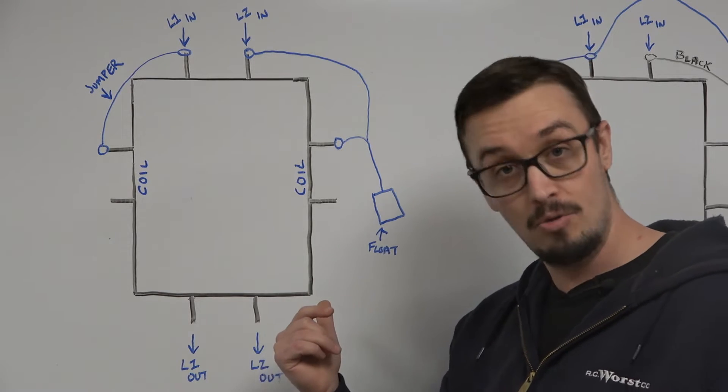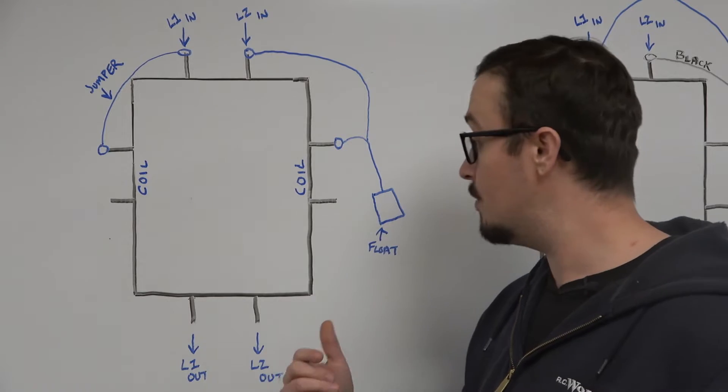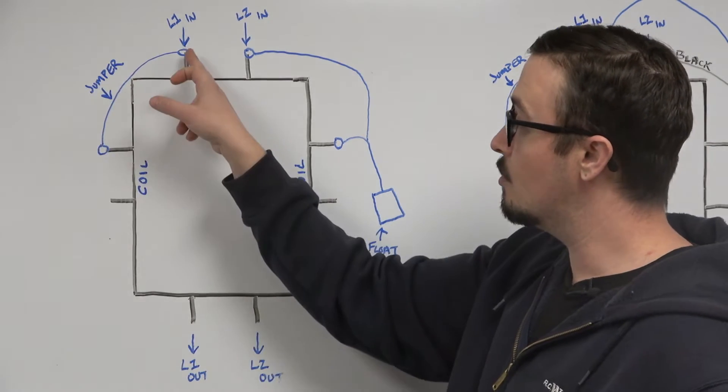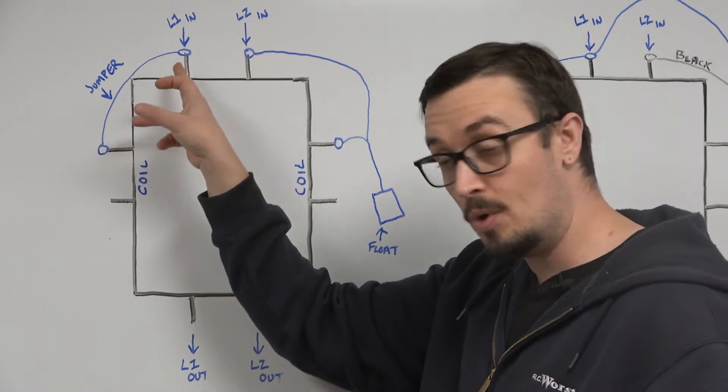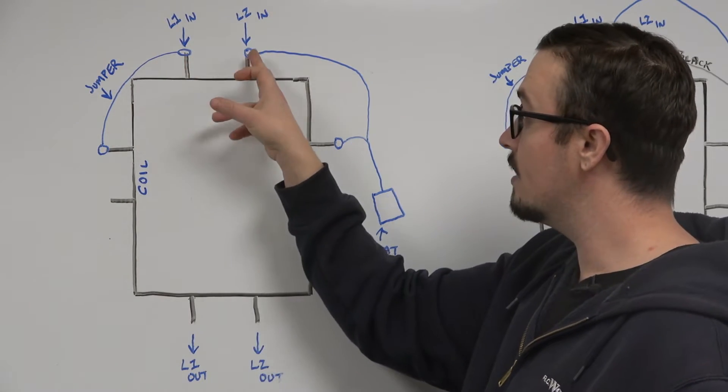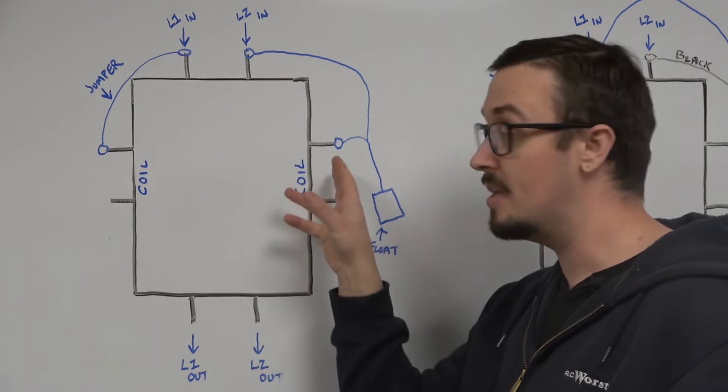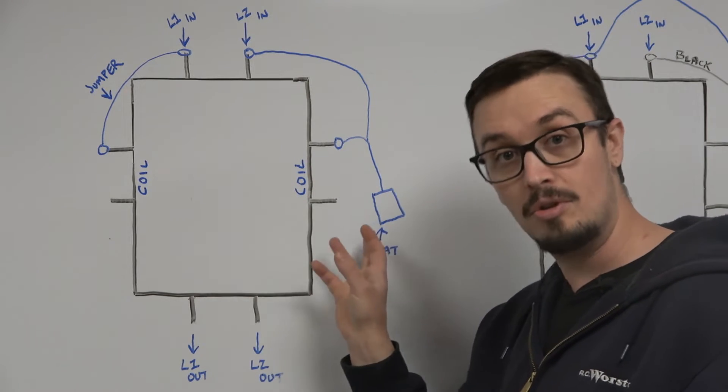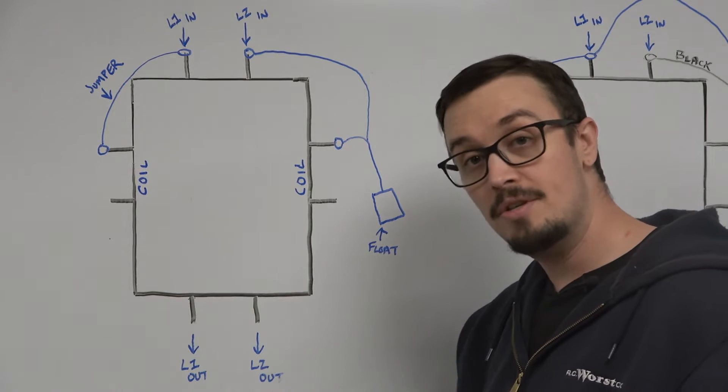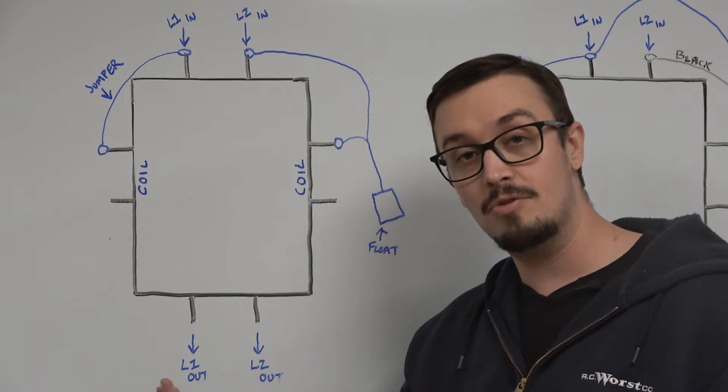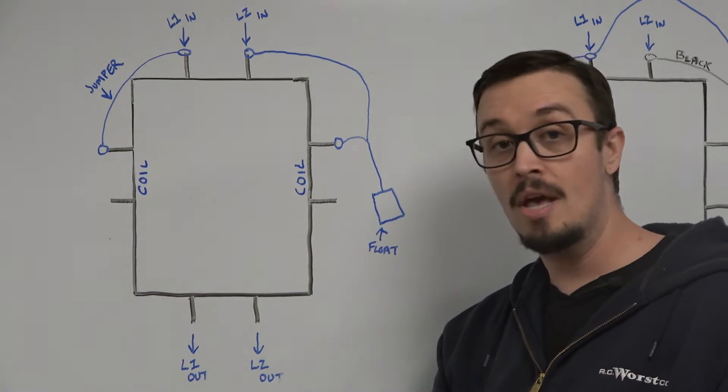So in this configuration we're jumpering the coil off of the incoming power from one side. Then we are running the other jumper essentially through the float switch which then engages the coil based on the float's closed condition. So it's a very simple setup but I know it's very common that people utilize contactors for these scenarios, so we figured we'd just show you guys how to wire one up.